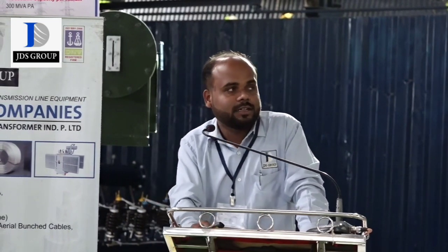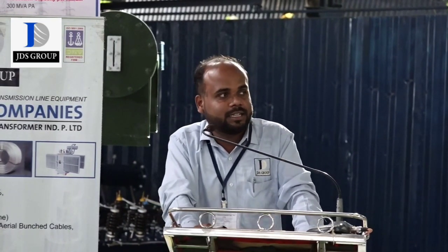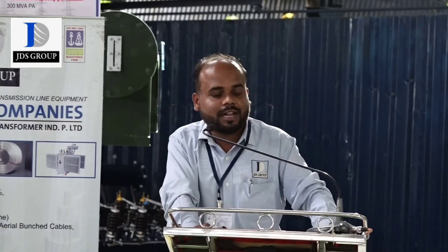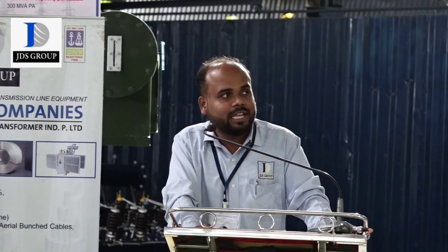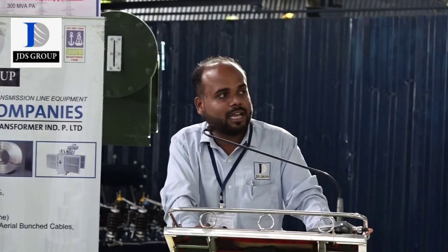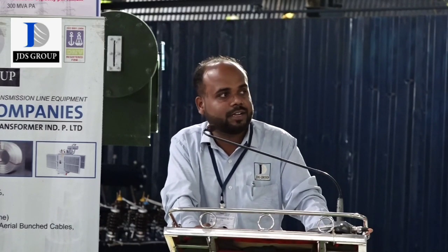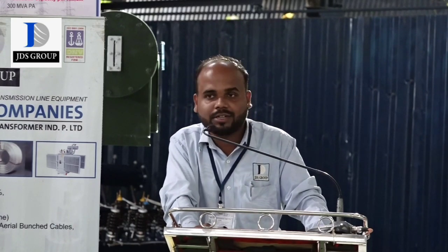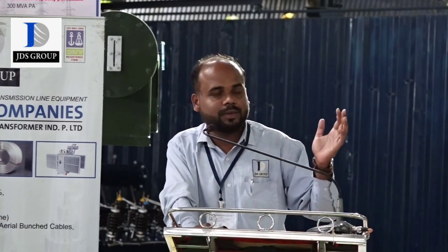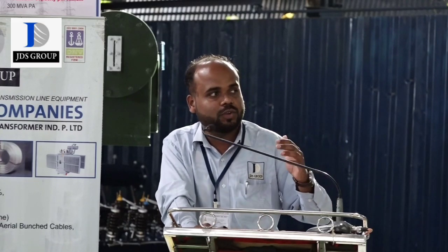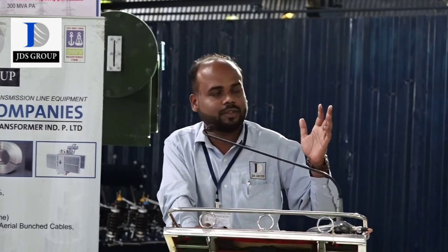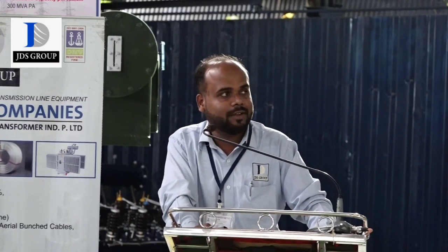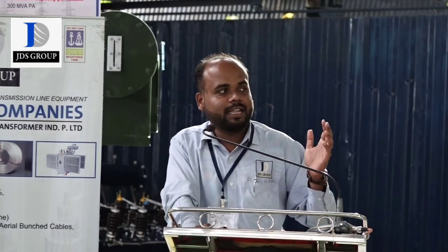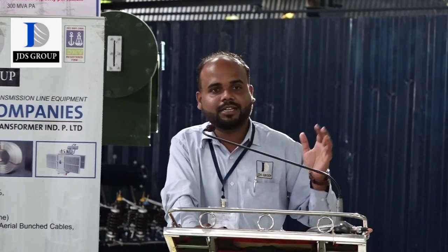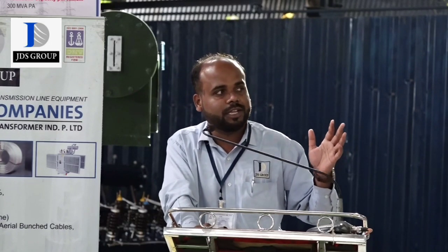After this stage, the main is the vector group range. Vector group means our distribution transformer is Dyn11. D stands for delta and Y stands for star, and 11 is the phase displacement between the two, that is 30 degrees. There is a clockwise representation between 10 and 11. So Dyn11 tells the vector group of the transformer. In a distribution transformer, we have the vector group of Dyn11.